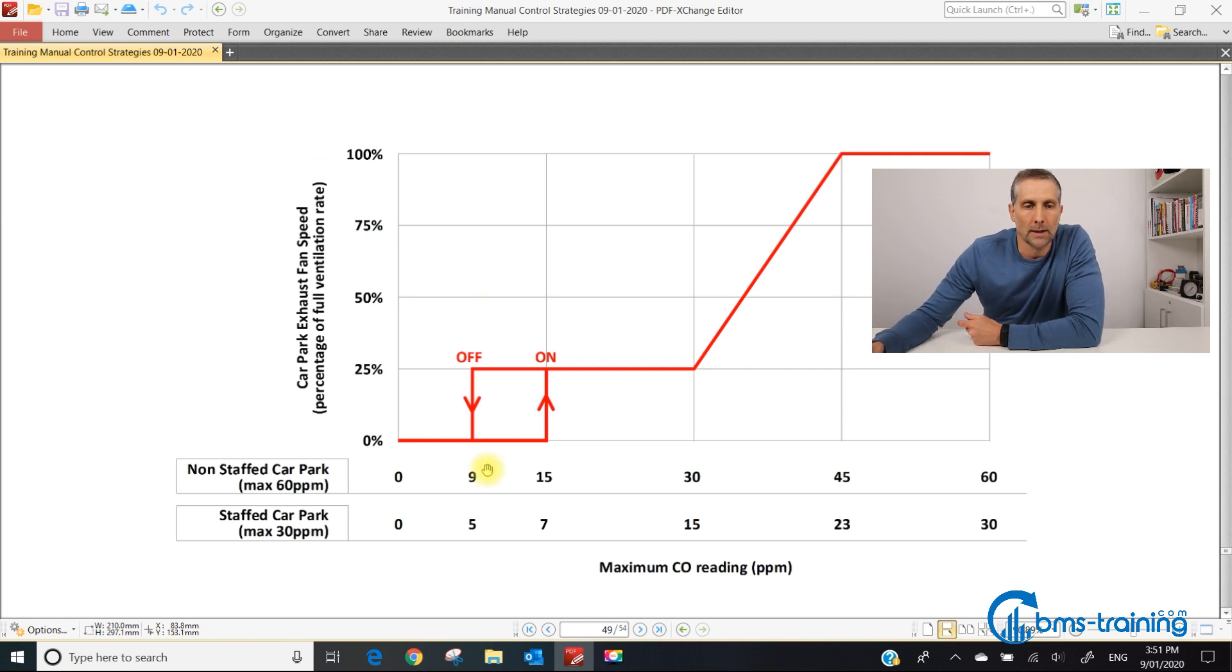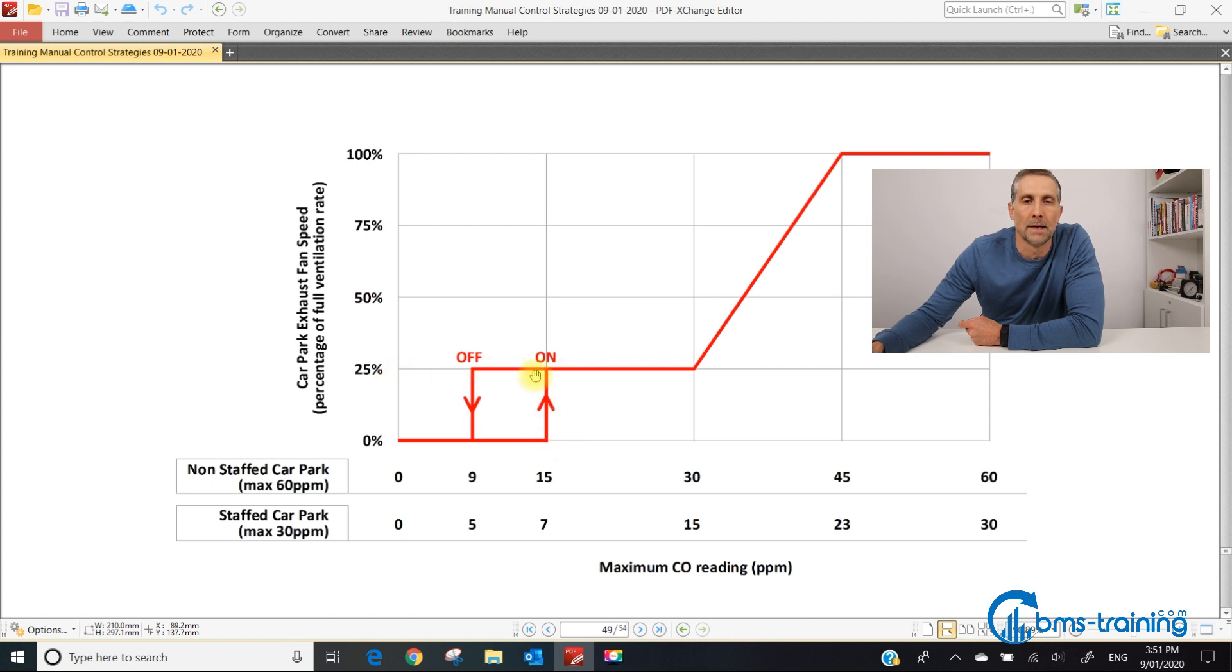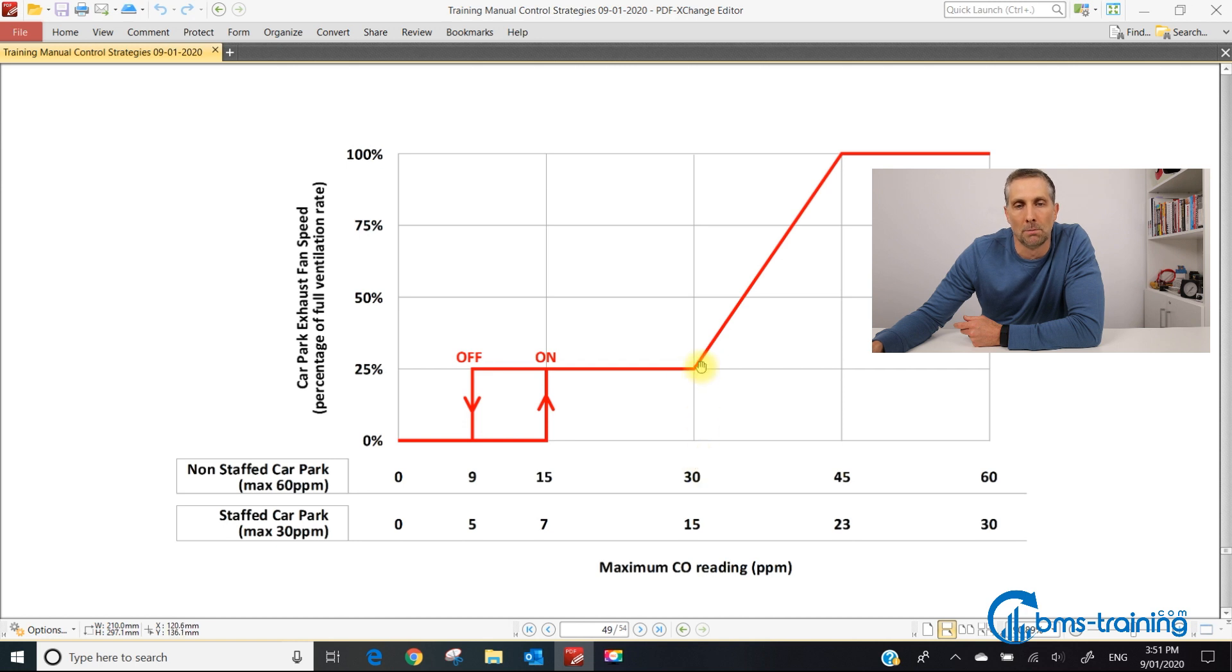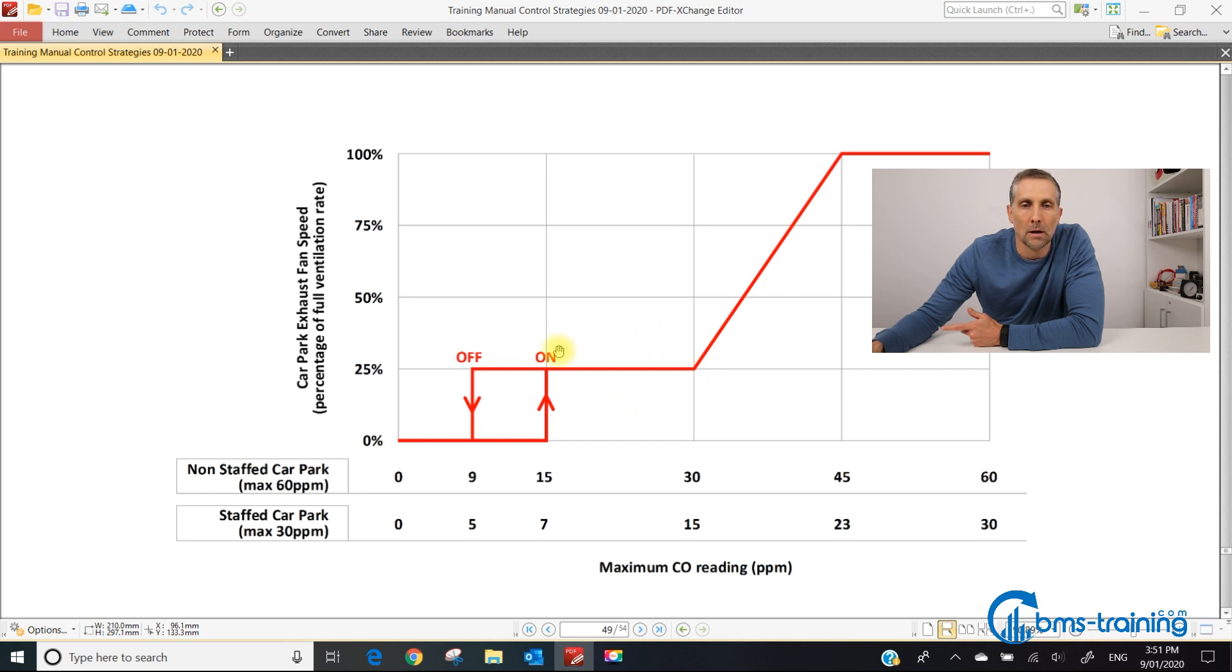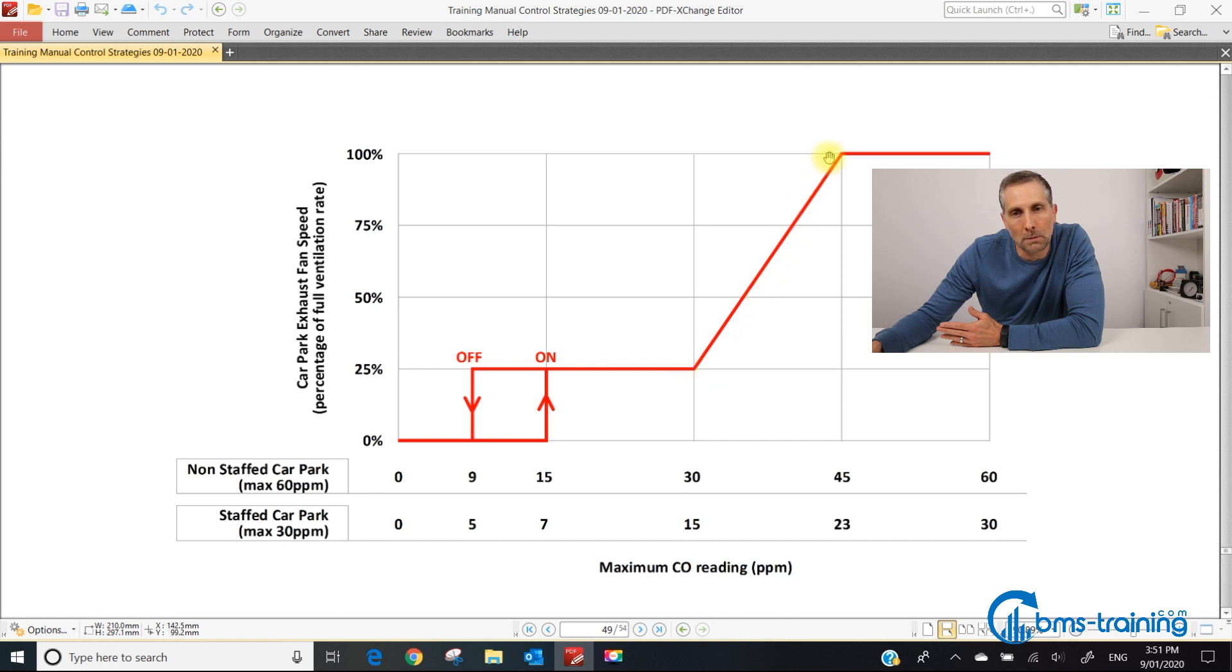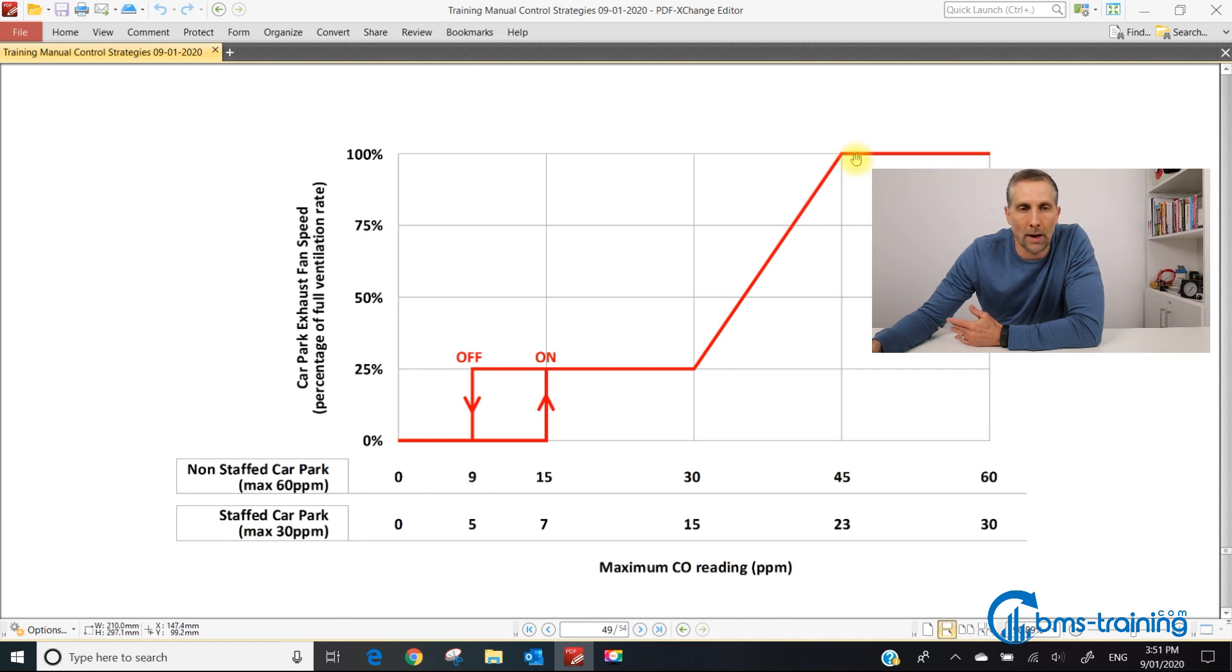As the maximum CO sensor increases above 15 parts per million, the VSD comes on and the fan runs at 25% minimum speed. It sits at minimum speed until the maximum CO reading increases above 30 ppm. This is really important because between 15 and 30 the fan sits at minimum speed, not doing anything energy efficient. It only ramps up from 30 to 45 ppm, then from 45 to 60 sits flat out at design speed.